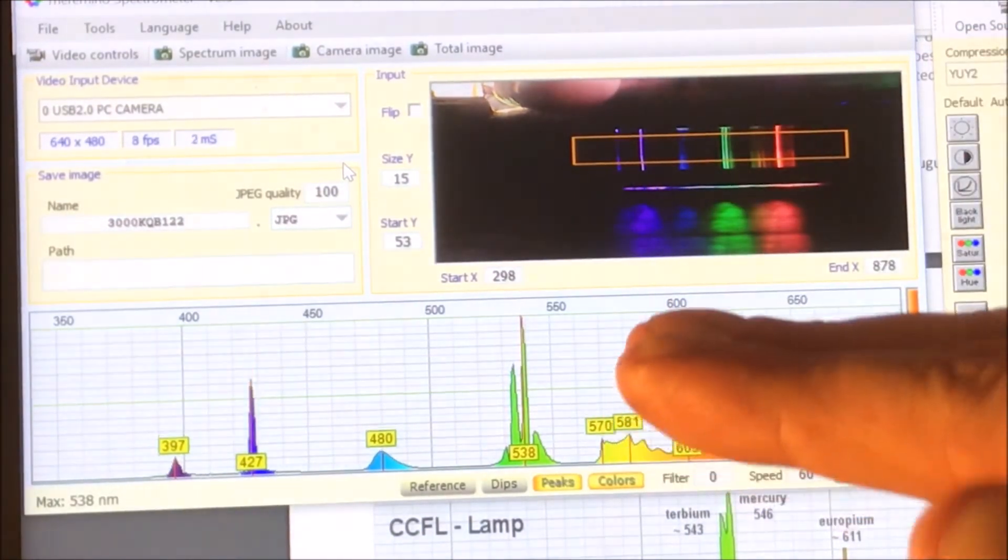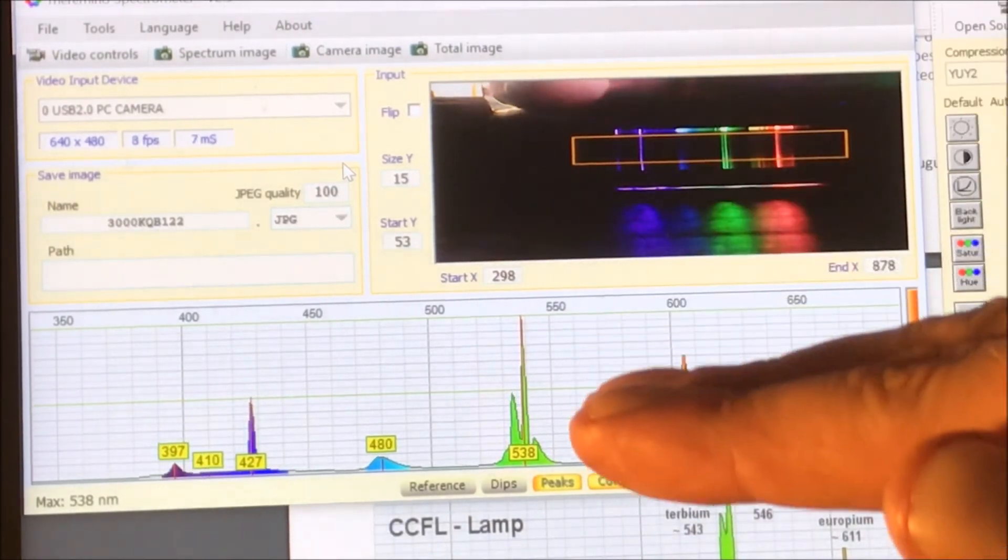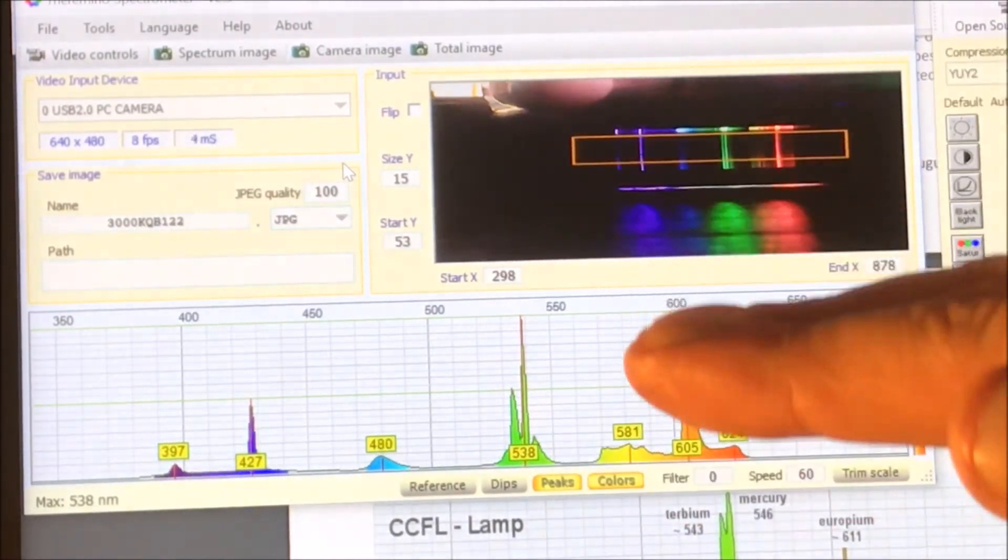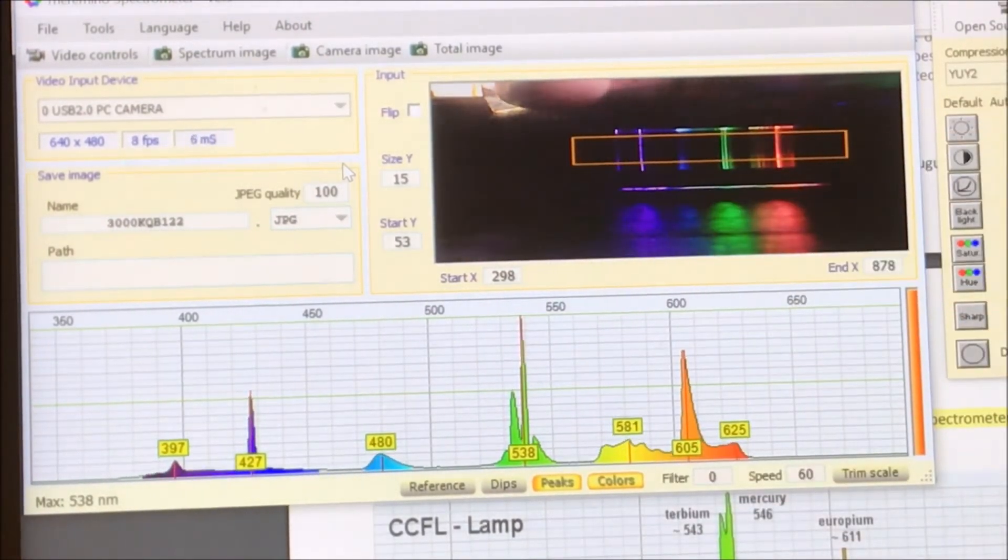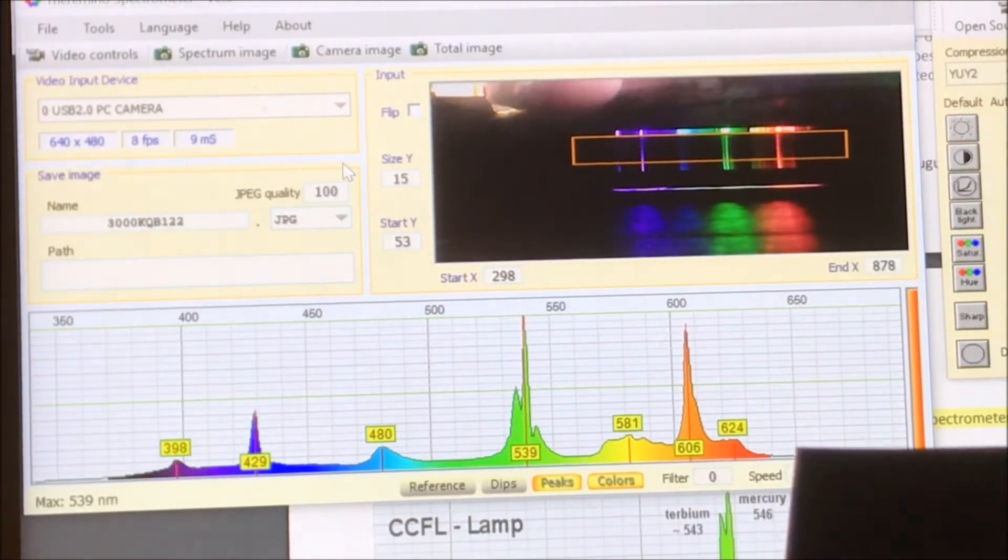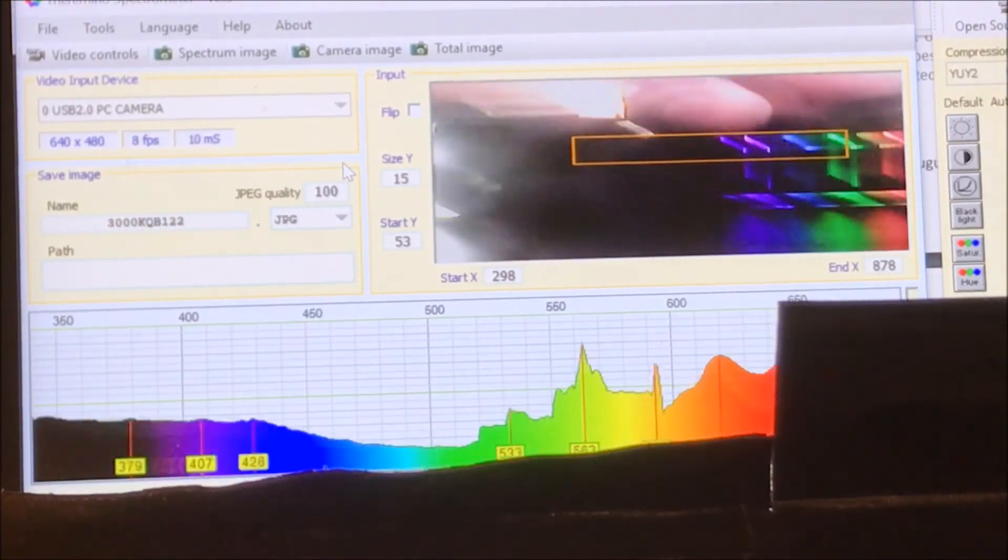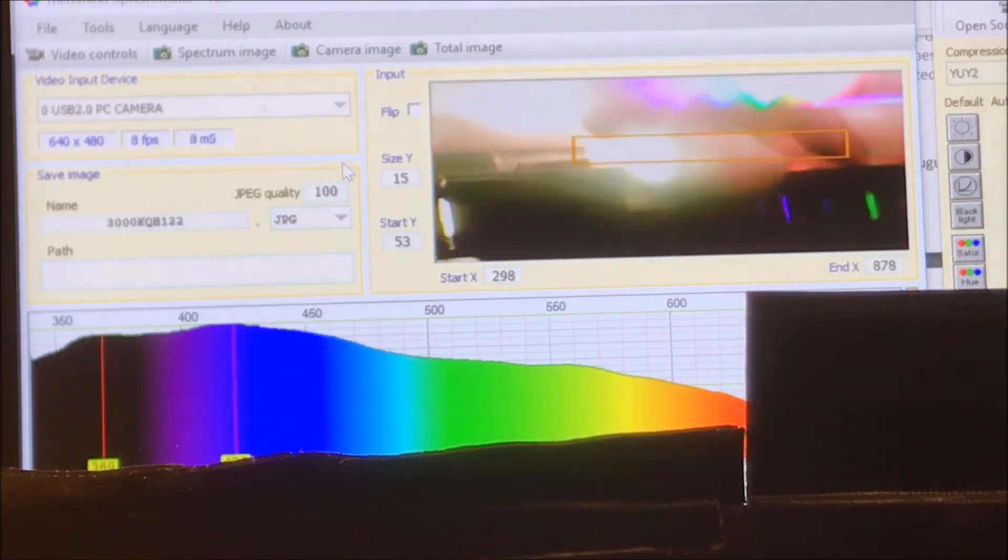If the lines on your spectral image are too close to the bottom or too close to the top, that means your relative position of the camera in respect to the slits is off. So if they're all the way at the bottom, that means that your camera is too high. So I can kind of simulate that for you guys here. It would look like that.